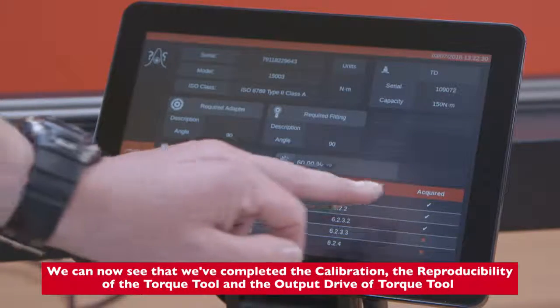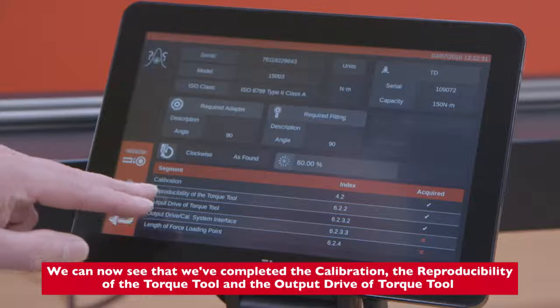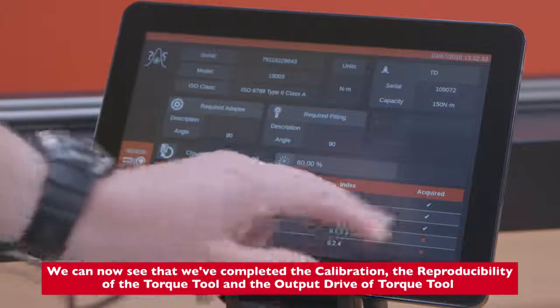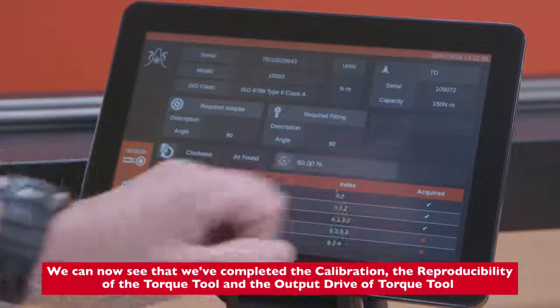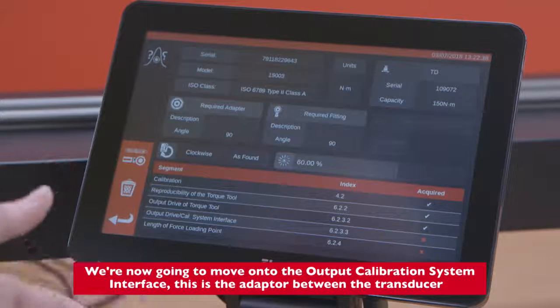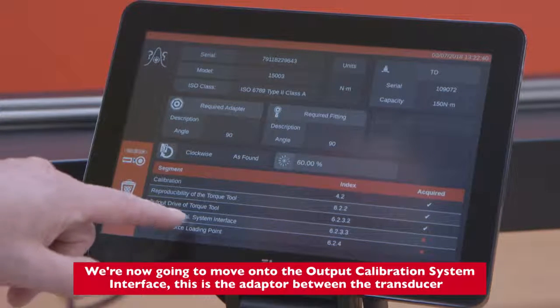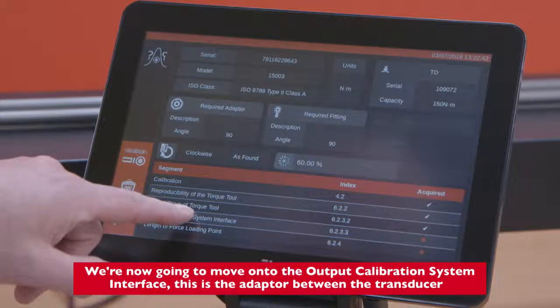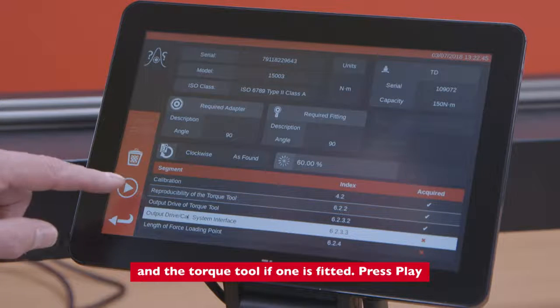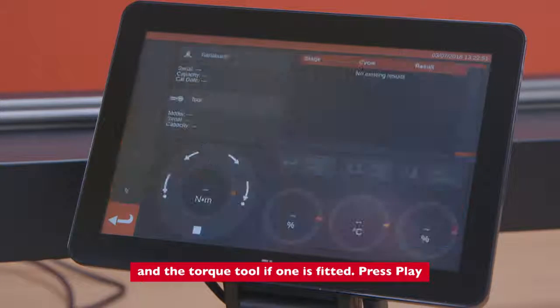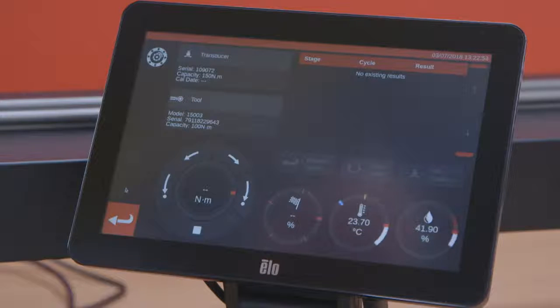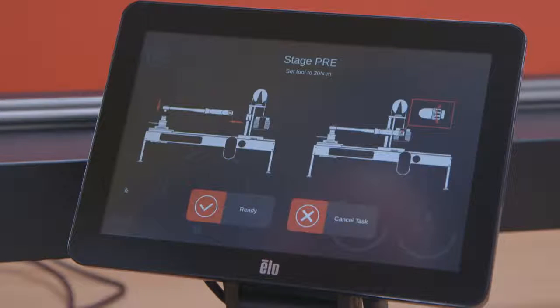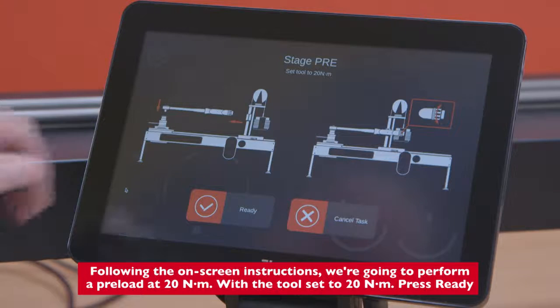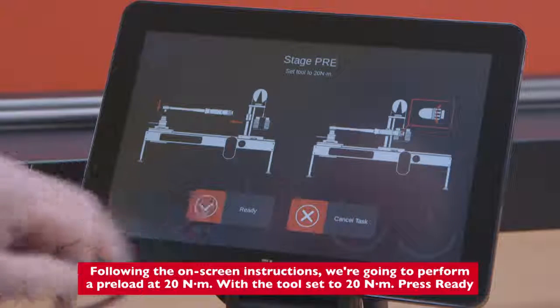We can now see that we've completed the calibration, the reproducibility of the torque tool, and the output drive of the torque tool. We're now going to move on to the output calibration system interface. This is the adapter between the transducer and the torque tool if one is fitted. Press play. Following the on-screen instructions, we're going to perform a preload at 20 Newton meters. With the tool set to 20 Newton meters, press ready.